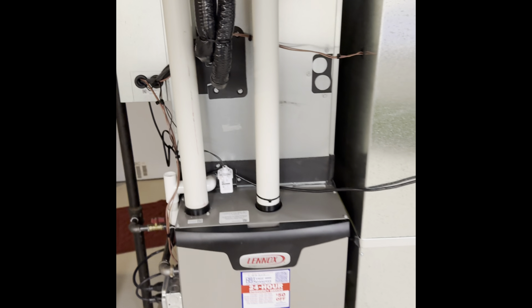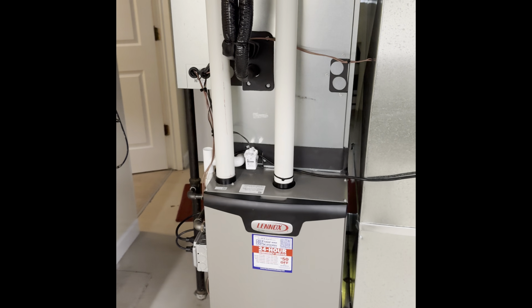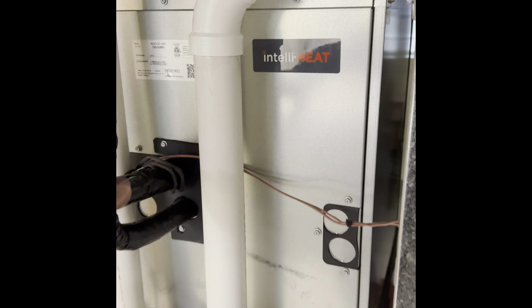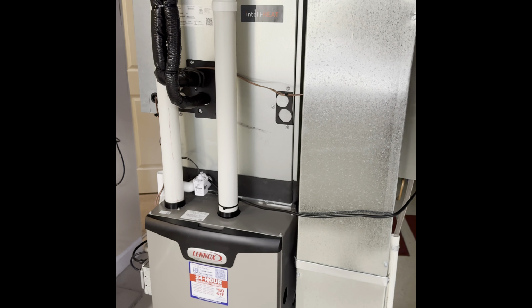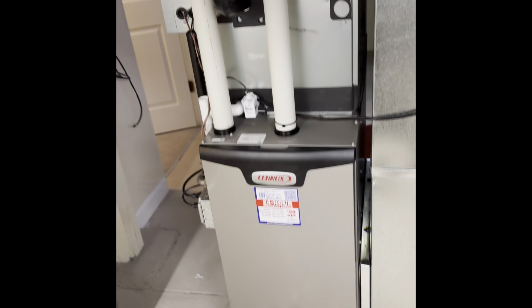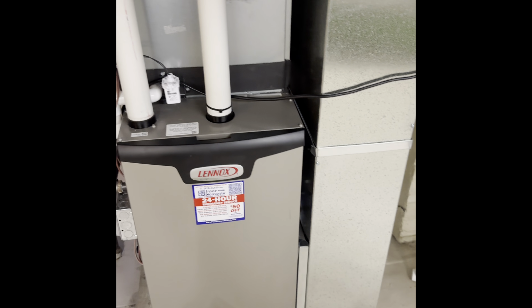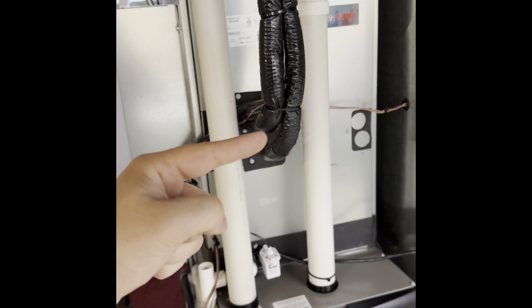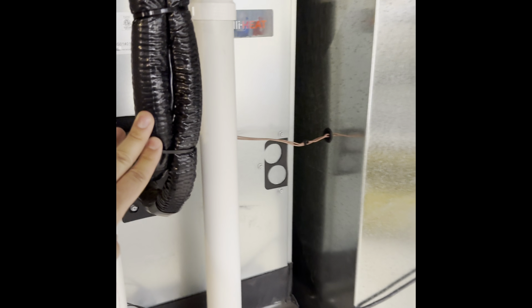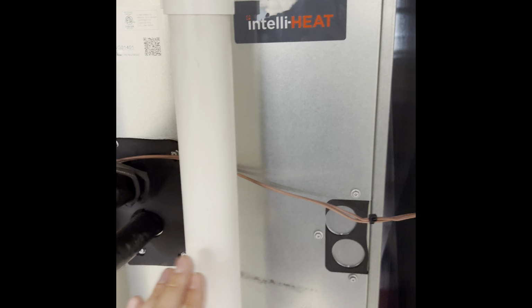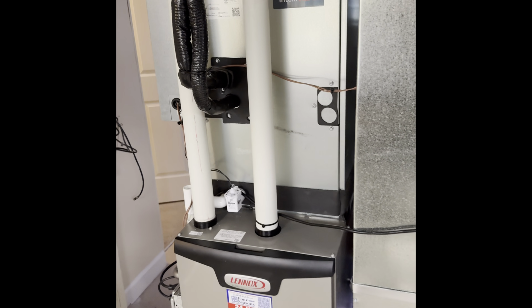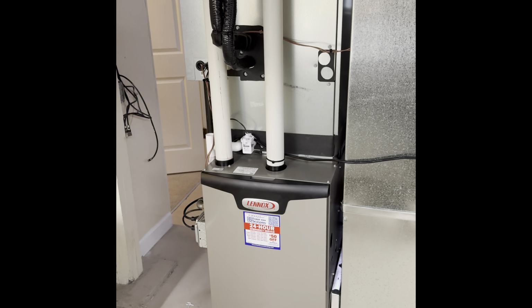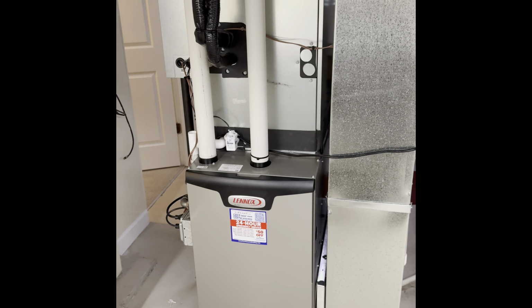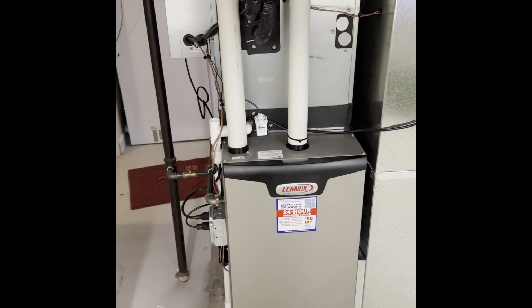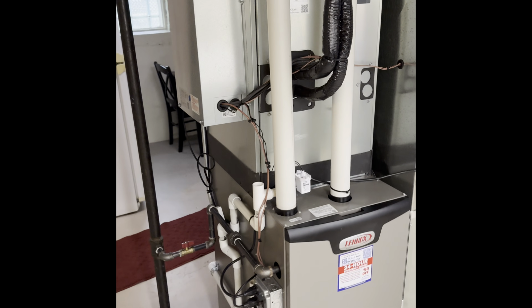Here's our control box. For this zone, the system again is running in cooling right now, but dual fuel. We have this coil programmed at 32 degrees, which means that whenever the outside temperature is 32 degrees or higher, all the furnace will have to do is run the blower, but all the heating will be produced by the outdoor unit, just warming the coil without using any gas. When the temperature drops, the furnace kicks in. This is fully adjustable, but we currently have it set at 32. So this is the first zone.